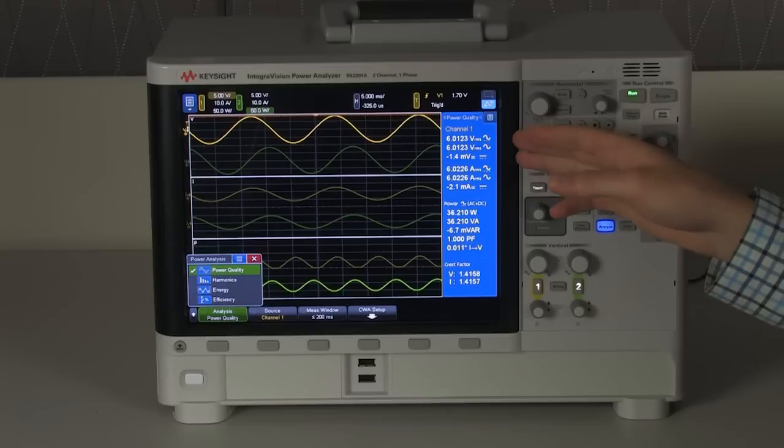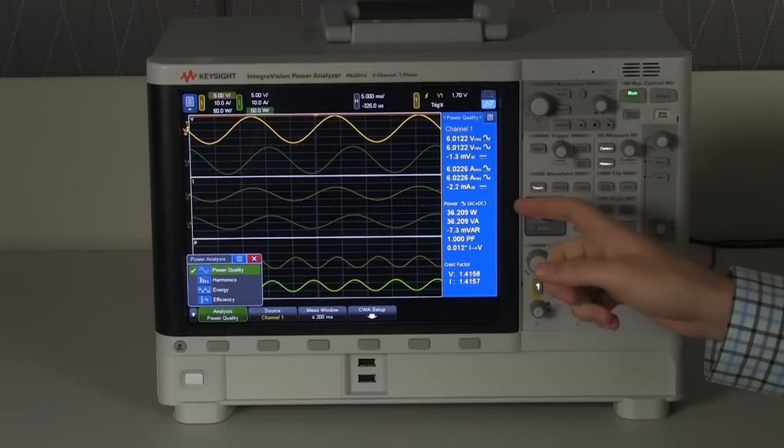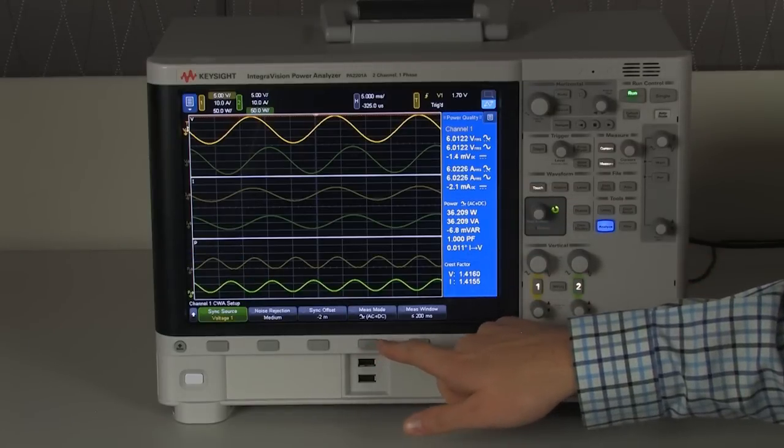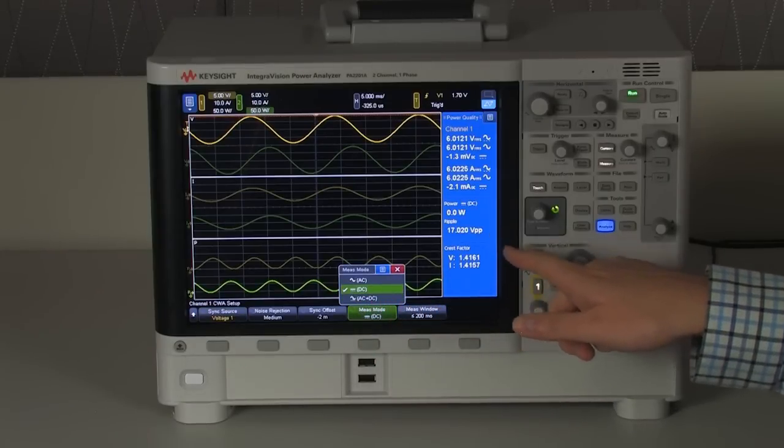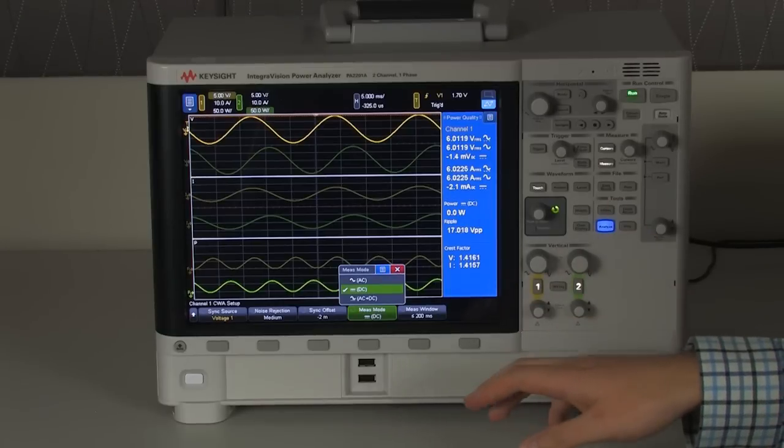Our first major menu is the power quality menu. We can measure AC voltage, AC current, DC voltage, DC current, instantaneous power, power factor, crest factor. And we can also change the mode to be DC-only mode. And we can then see the ripple on our DC power supply if we were using one to know how good of a quality power supply it is.